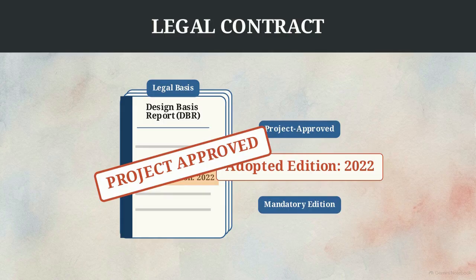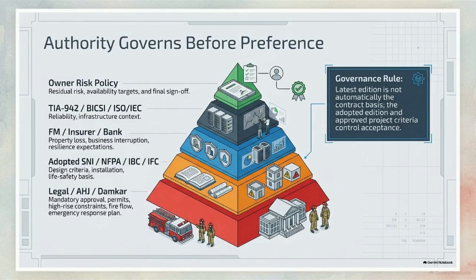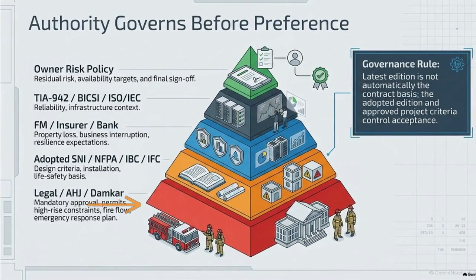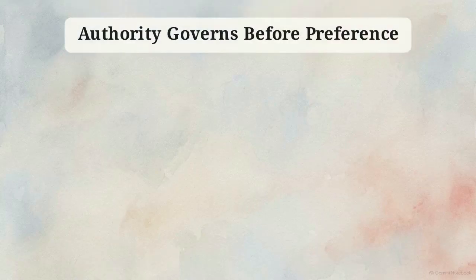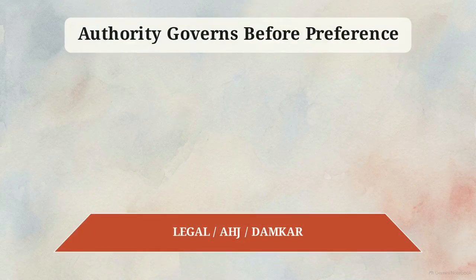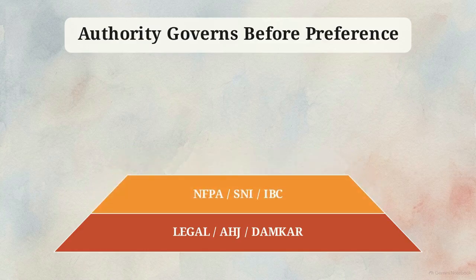the actual legal contract. To understand what actually governs a facility, we use this 5-tiered standards hierarchy. The bottom 2 tiers form our uncompromisable bedrock. The red layer represents local laws, the authority having jurisdiction, and the fire brigade, or Damkar. These dictate mandatory building permits, fire access, and water supply.